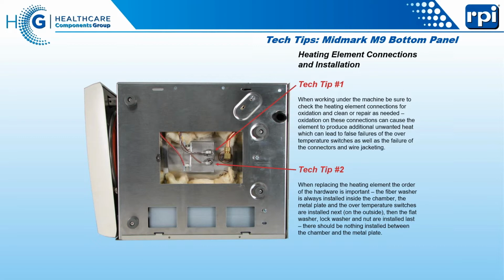So first one, when you're working under the machine, for any reason, take a look at what you've got going on under here. You might find that there are leaks around these gaskets where the heating element goes through the wall of the chamber. There are also wires that can become oxidized and start to become brittle or frail. We want to keep an eye on that. If you do see that, there are washers that can be replaced.